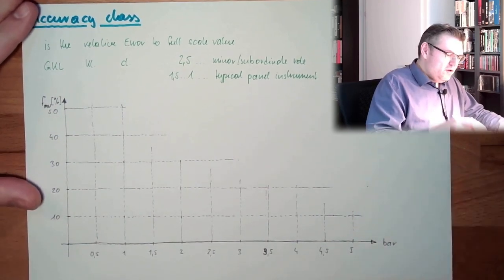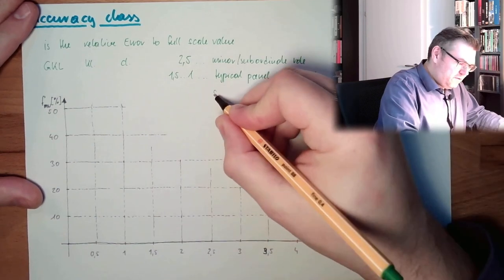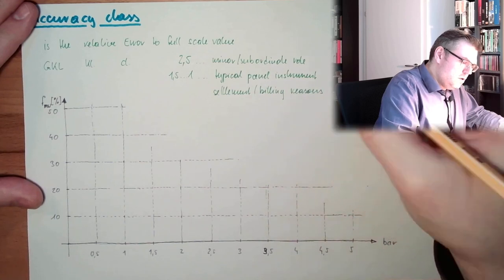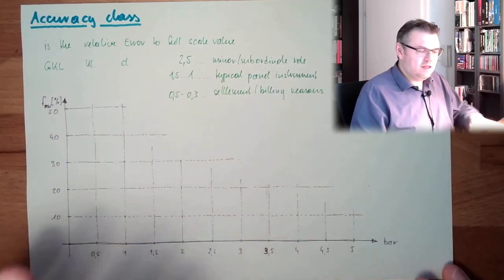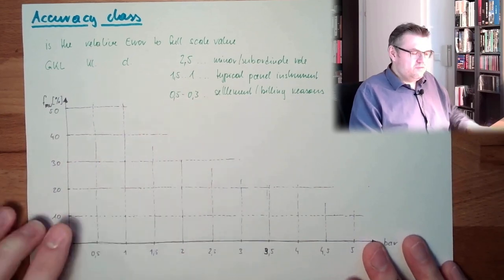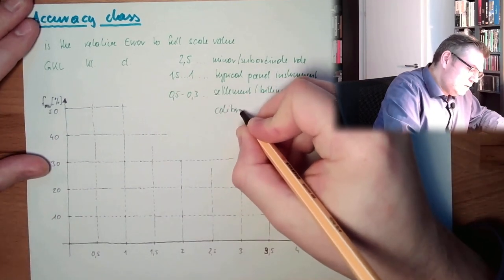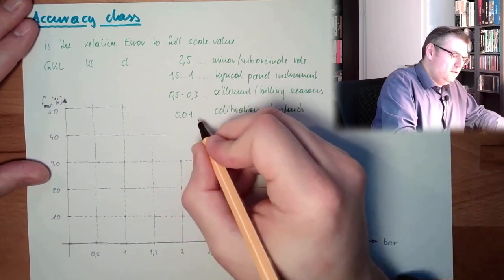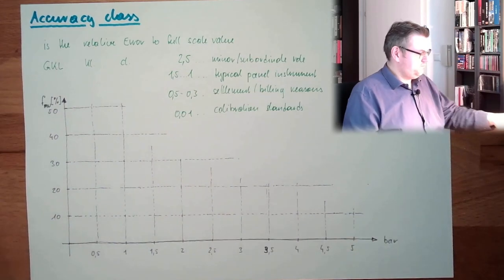If you have at home, there is some settlement reasons, billing. There, in a way, 0.5 to 0.3. This is the typical class of these. So 0.5% error, maximum. This is for settlement reasons. And calibration standards? They are at 0.01. These are typical class values.